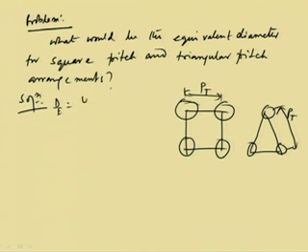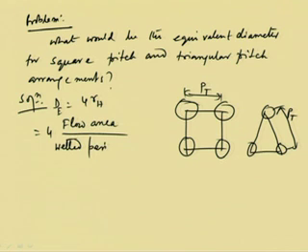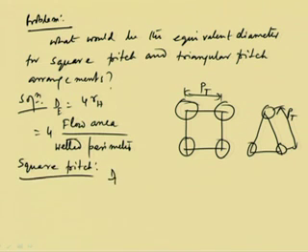It is equal to 4 times the hydraulic radius, and that is equal to 4 into flow area. Hydraulic radius is defined as flow area by wetted perimeter. Okay. So in case of tube arrangements, for square pitch, D equivalent will be equal to 4 times flow area, and flow area would be equal to PT square minus pi d square by 4 into 4.